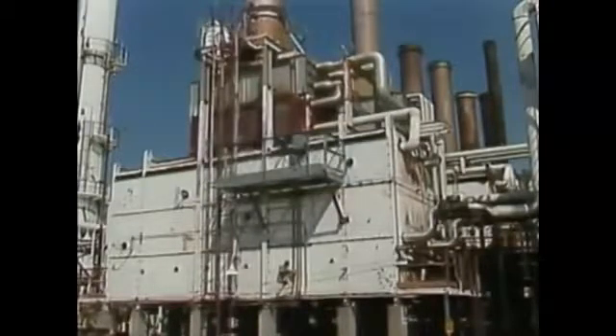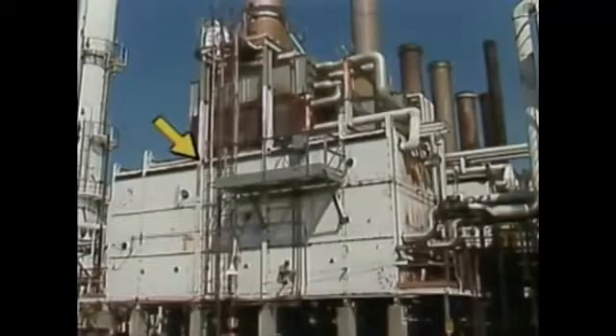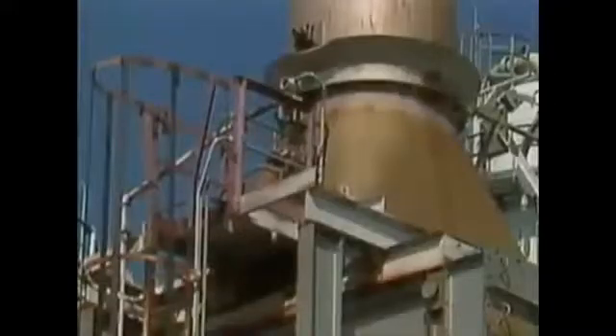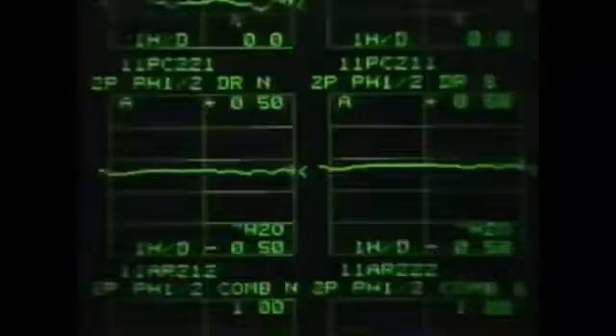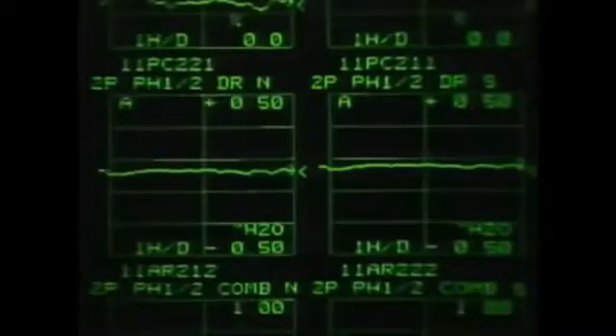In this case, there are pressure transmitters that measure draft at the top or arch of the radiant section and at the base of the radiant section, in the firebox — the area where combustion occurs. Draft may also be measured in the stack, typically at a point below the stack damper. Draft is usually measured in inches of water, and the draft gauge reading should be correct for all of the areas in the furnace.